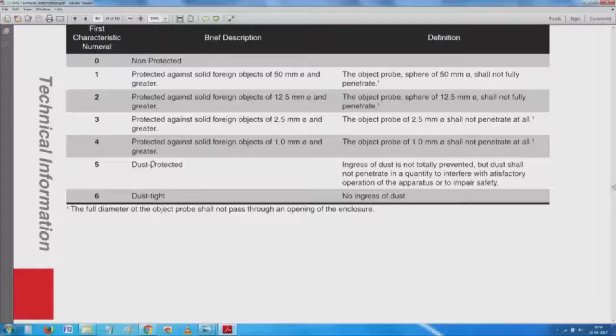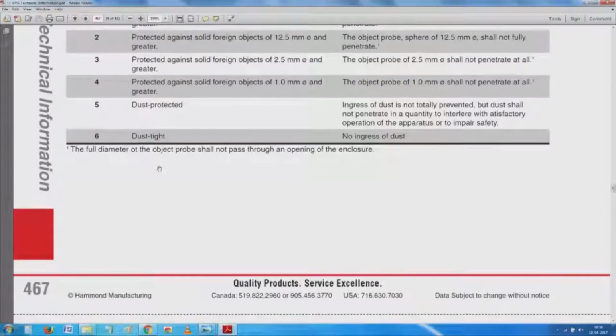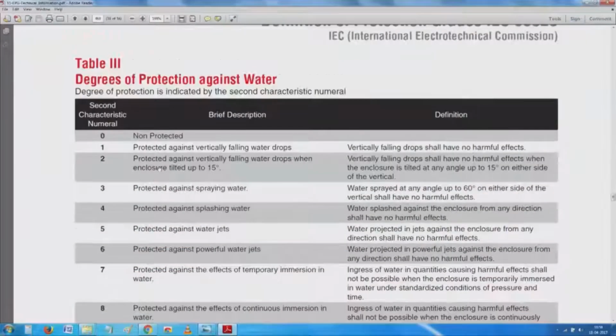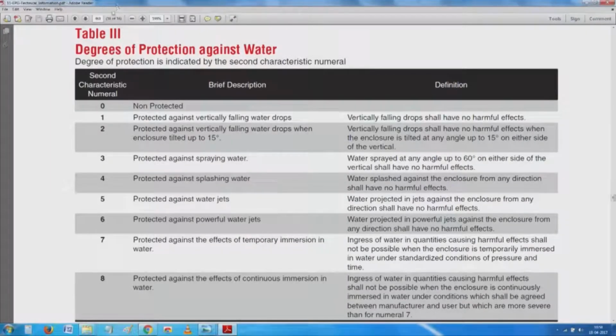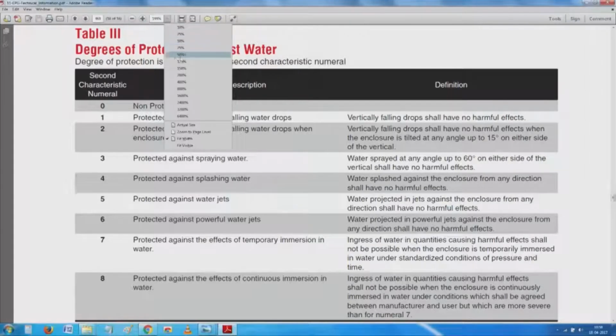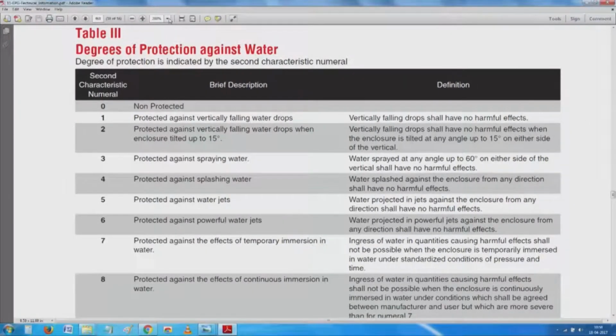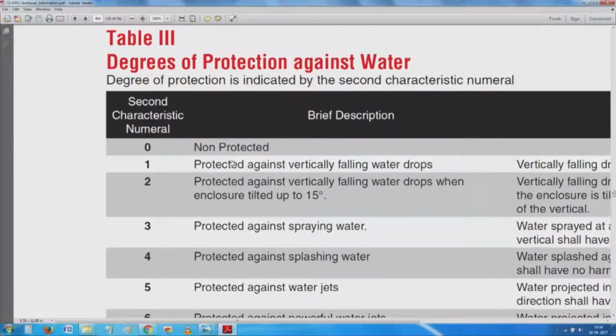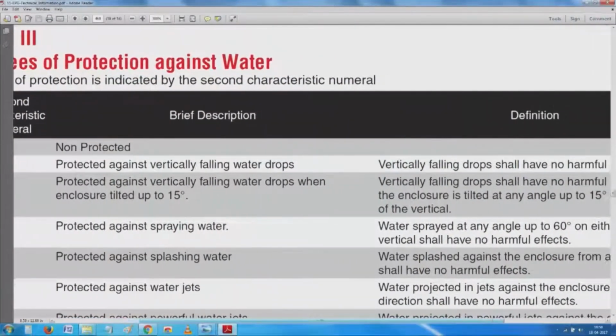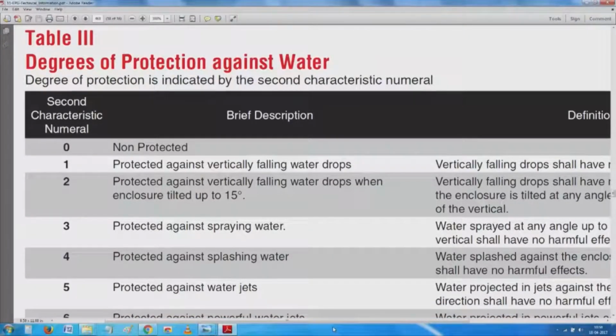You see here, as we come here, we come into 5 and 6, which talk already about something being dust tight. We are coming into liquids. Not protected completely. The first thing is saying the ingress of water, nothing is taken care of by the ingress of water. Should some water fall inside, nothing will happen.